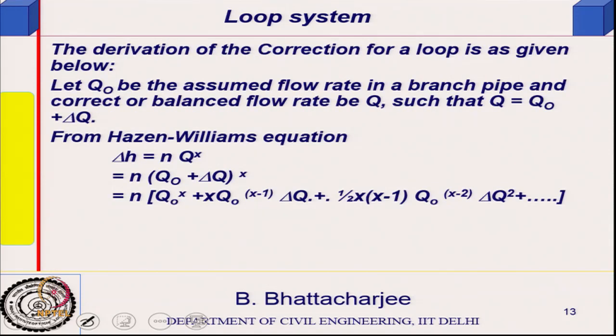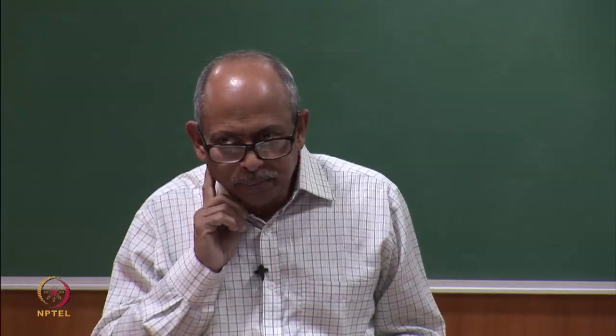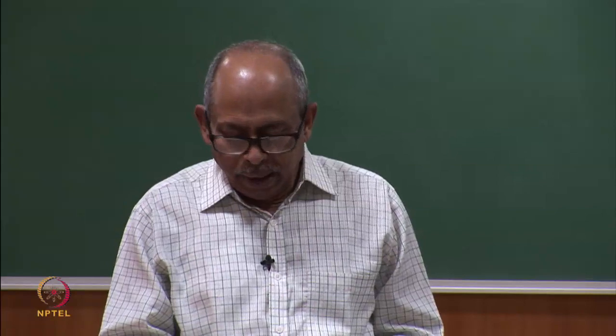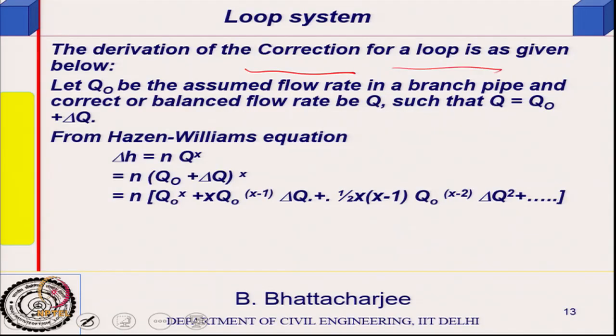In the Hardy-Cross method, the basic equation requires finding Σhf in a loop — that should equal zero; if not, that is the error and a correction ΔQ must be applied. Assume q₀ as the initial flow rate in a branch pipe and correct to the balanced flow rate. We will derive the expression for ΔQ, the correction term.